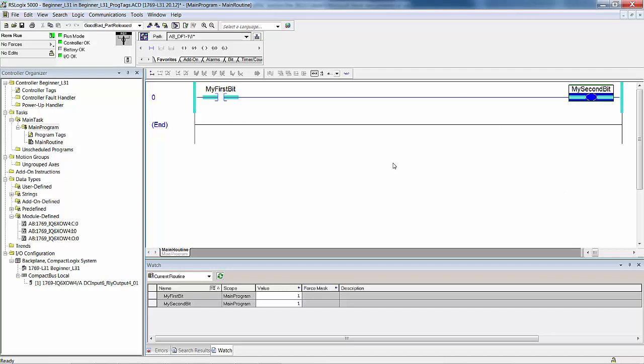In the book, I said, did the controller's memory accept the value of 0? Well, again, you could say yes or no. I would just say no because you couldn't see it. Did the tag remain at 0? No. Why? Because the program is executing every 20 microseconds, and although you have access to the database from your keyboard, the program is quicker than the keyboard.